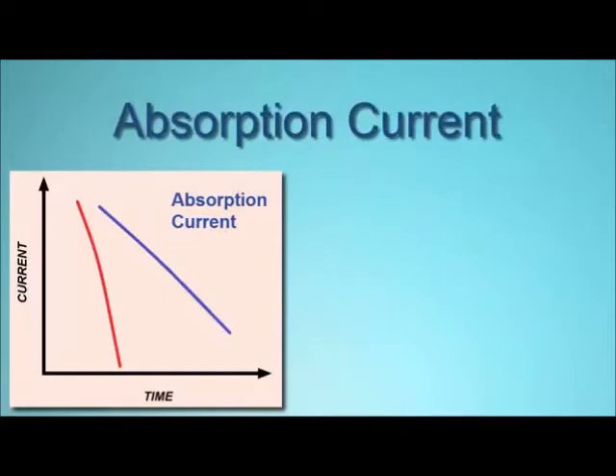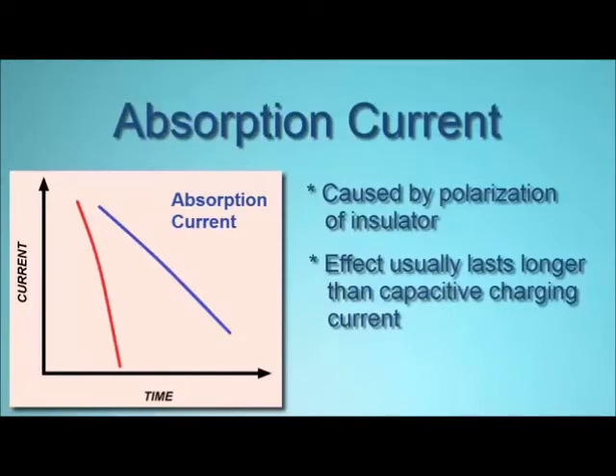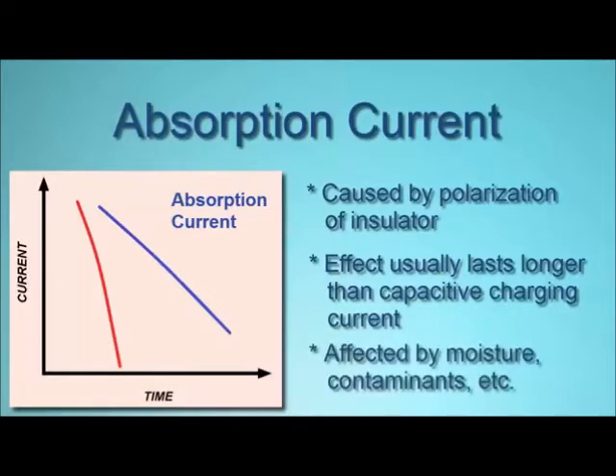Absorption current, also called polarization absorption current, is caused by the insulating material becoming polarized by the electricity flowing through the conductor. As the polarization level increases, the absorption current decreases. This gradual change reflects the storage of potential energy in and along the insulation. As a result, resistance is initially lower and then rises. This produces a measurement profile similar to capacitive charging current, but at a much lower rate. The effect can last several seconds up to a minute or more. The length of time it takes for absorption current to fall off can be affected by moisture or other contaminants in the insulation material. Therefore, absorption current is an important indicator of insulation integrity.